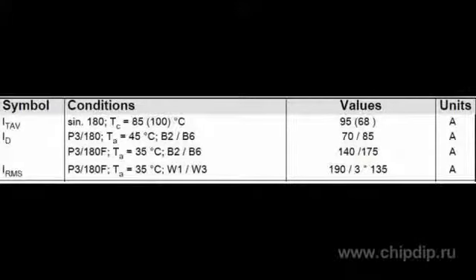Continuous IRMS current exceeds the average current IT-AV by 2 times, which characterizes the minimal loss of power on the resistive elements of the thyristor, including power leads. The maximum critical rate of increase of commutation voltage is at least 1,000 volts per microsecond.